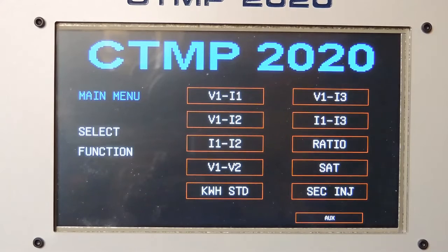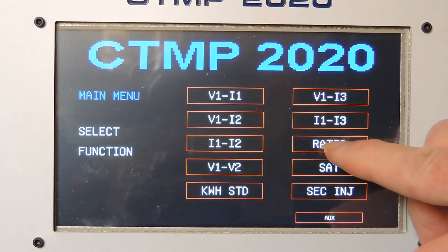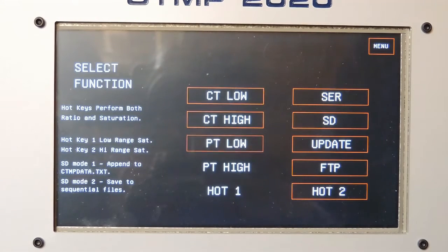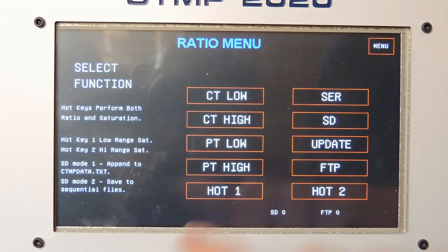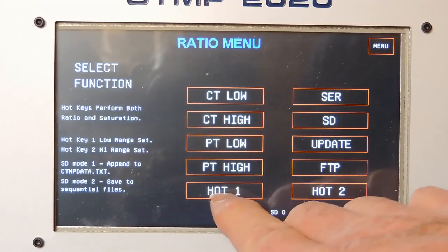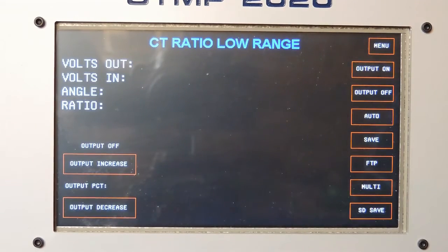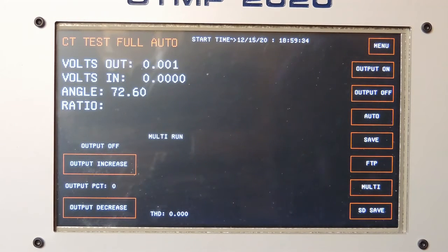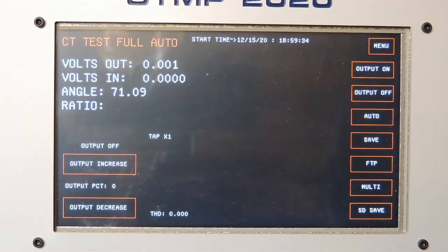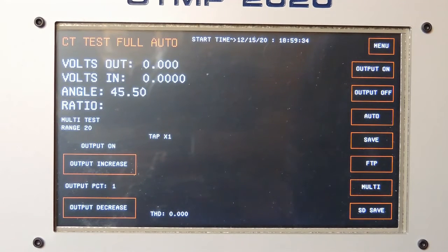So what if I wanted to do a ratio on this? I just selected ratio and I selected hot one. The normal target is .1 volts, but this won't make .1 volts per turn without being deeply saturated. So what will the test set do?